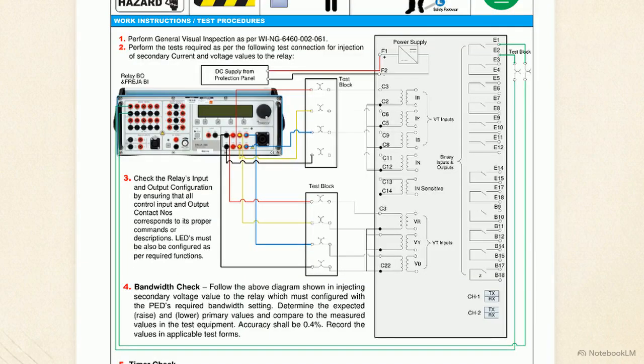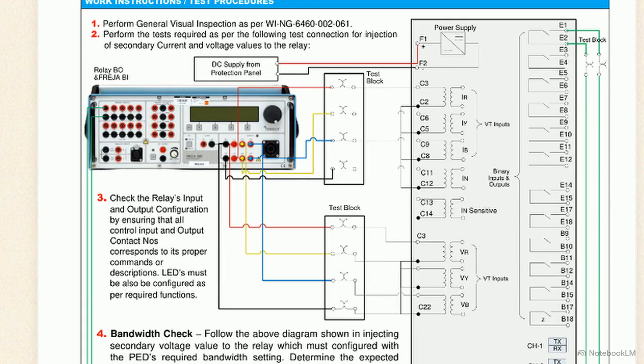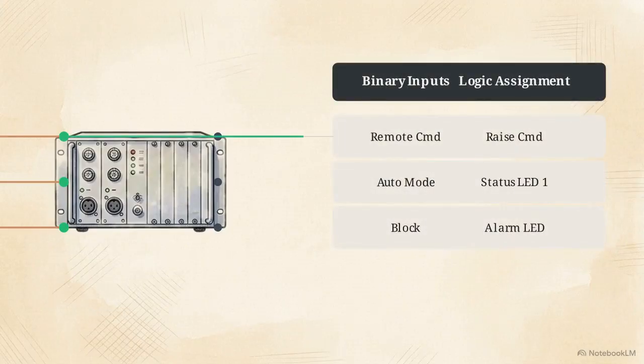Moving to the second module, we isolate the relay and execute secondary injection tests to verify bandwidth and timers. This diagram maps the required test kit connections. You connect the secondary voltage and current injection circuits to the relay entirely through the designated test blocks, isolating the device without disturbing in-service wiring.